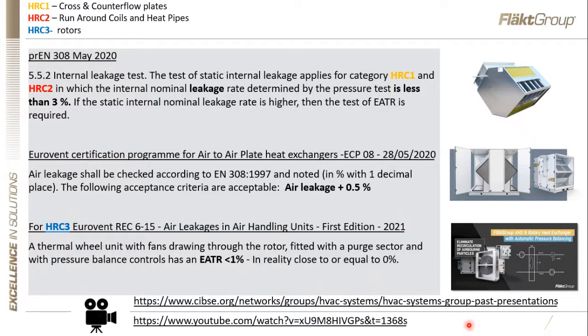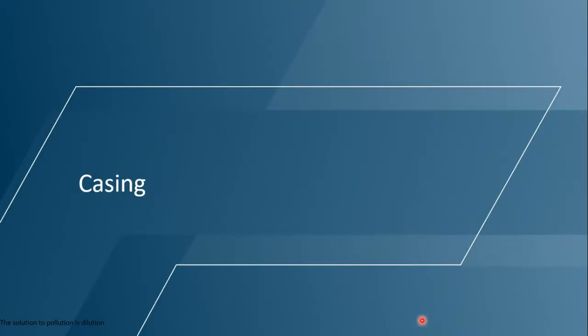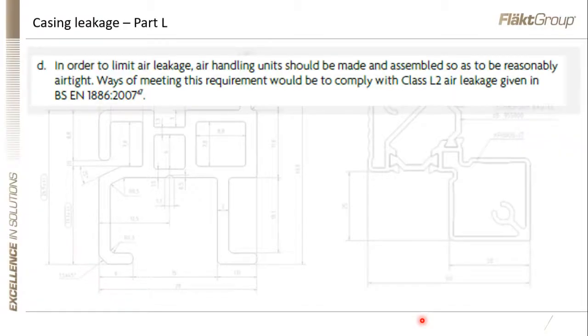And if you want details of that previous presentation, they're actually on the HVAC Systems Group webpage, and there is a YouTube link as well here in this presentation. So what about the casing? Well, the casing, we're obliged for Part L compliance to comply with EN 1886, which defines the leakage standard for the air handling unit, and of course this will be revised shortly. We must achieve Class L2 leakage for air handling units.